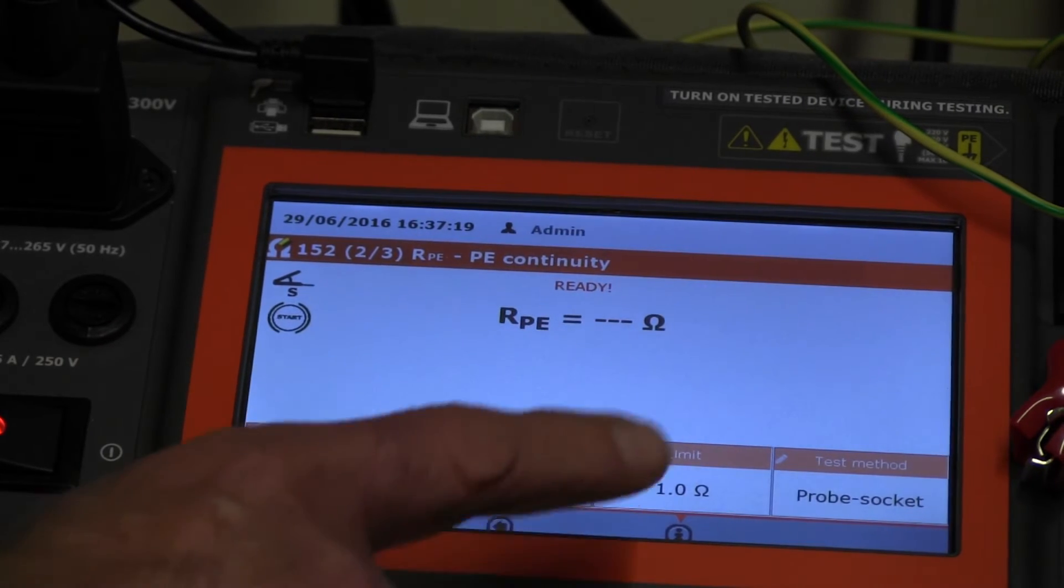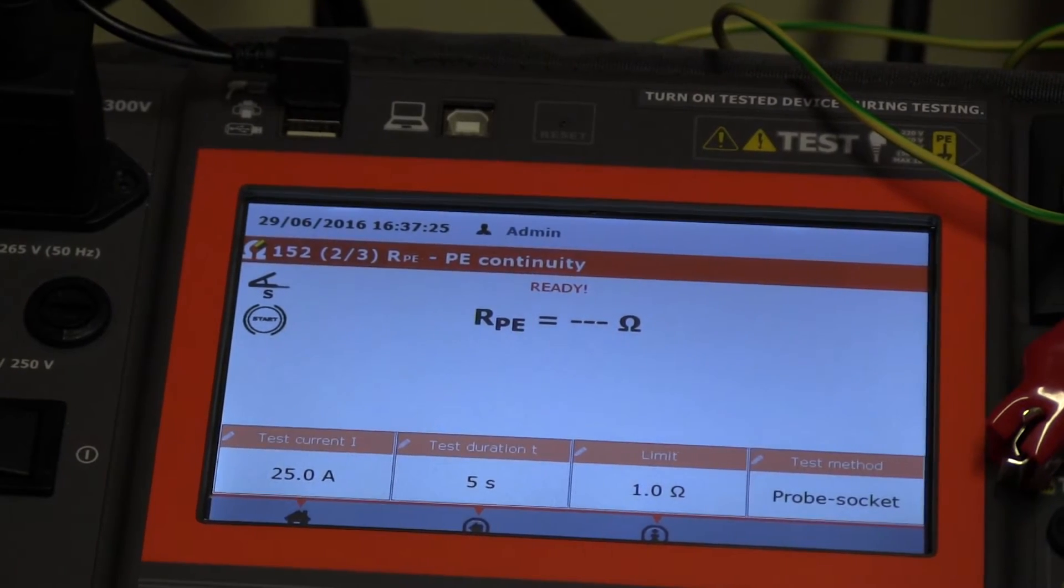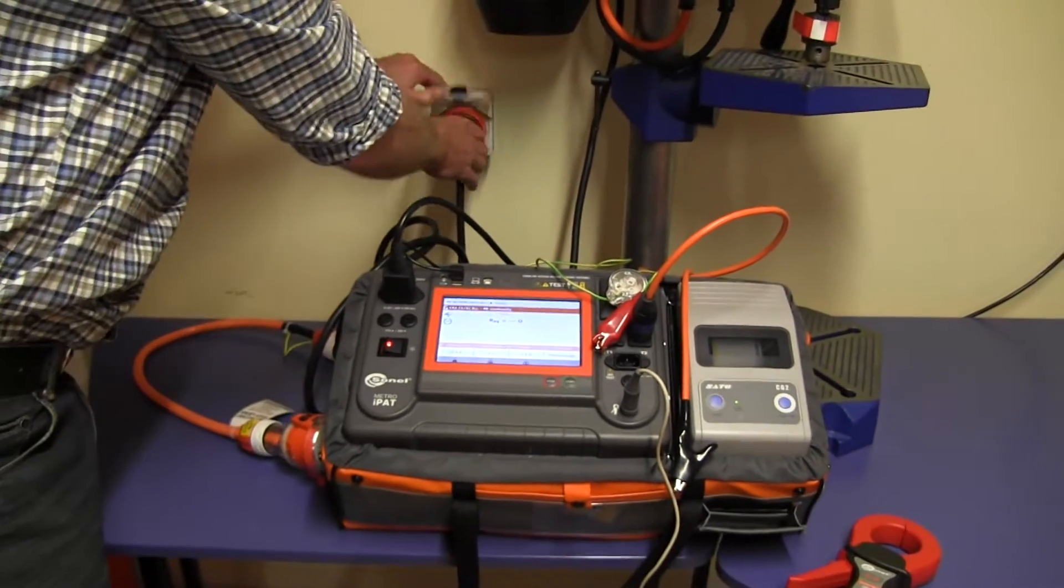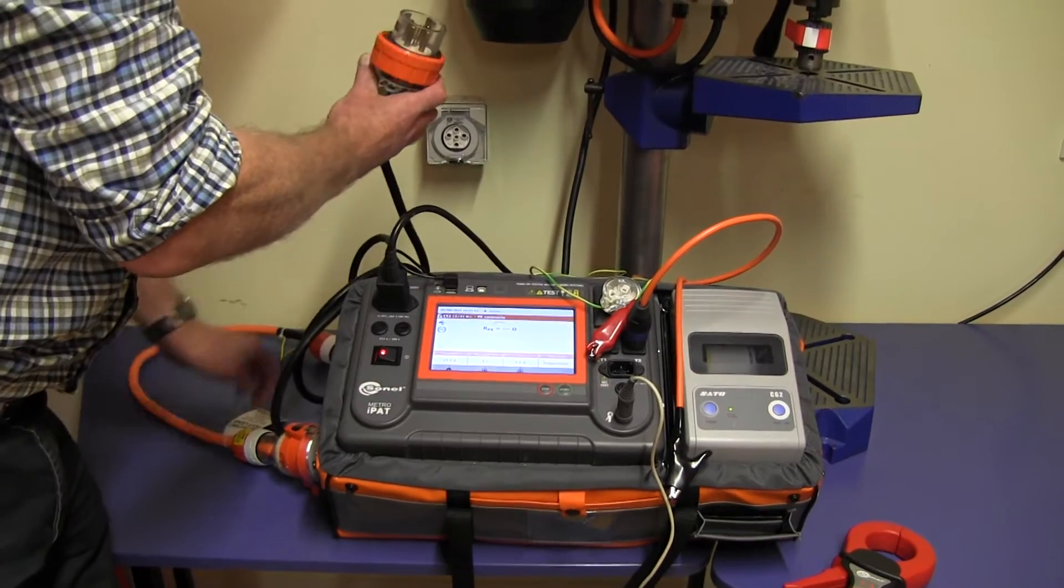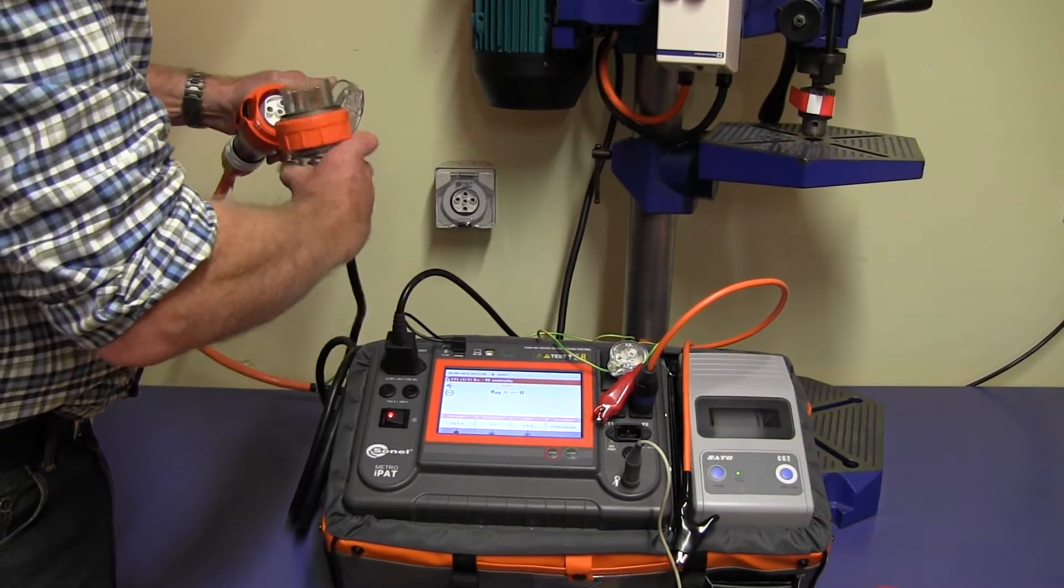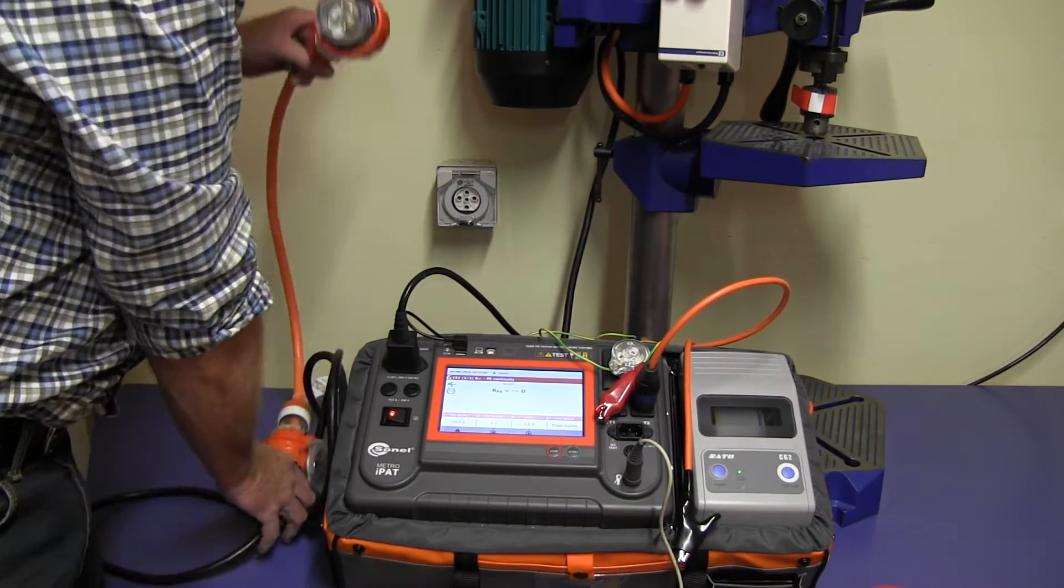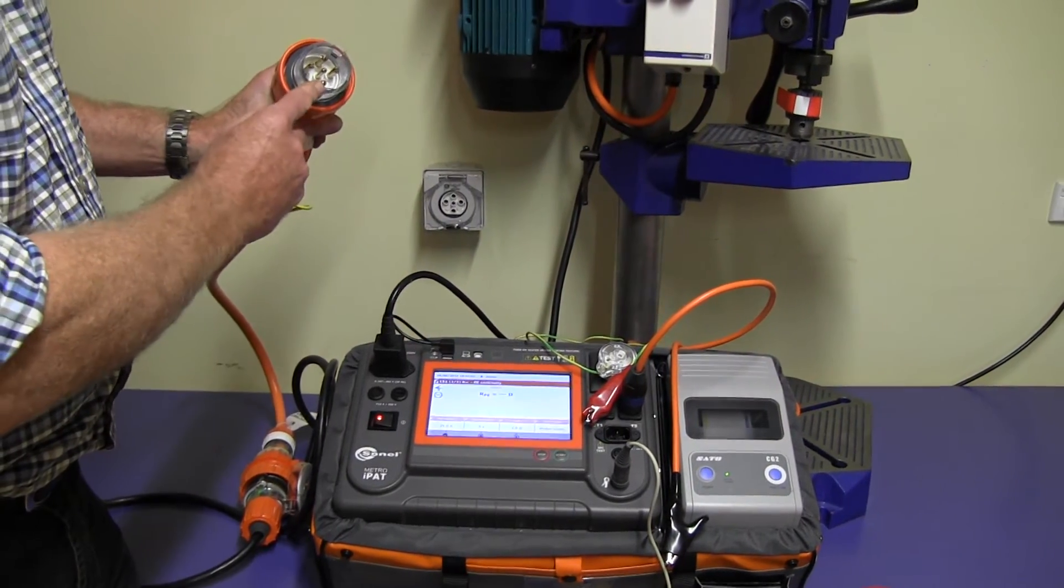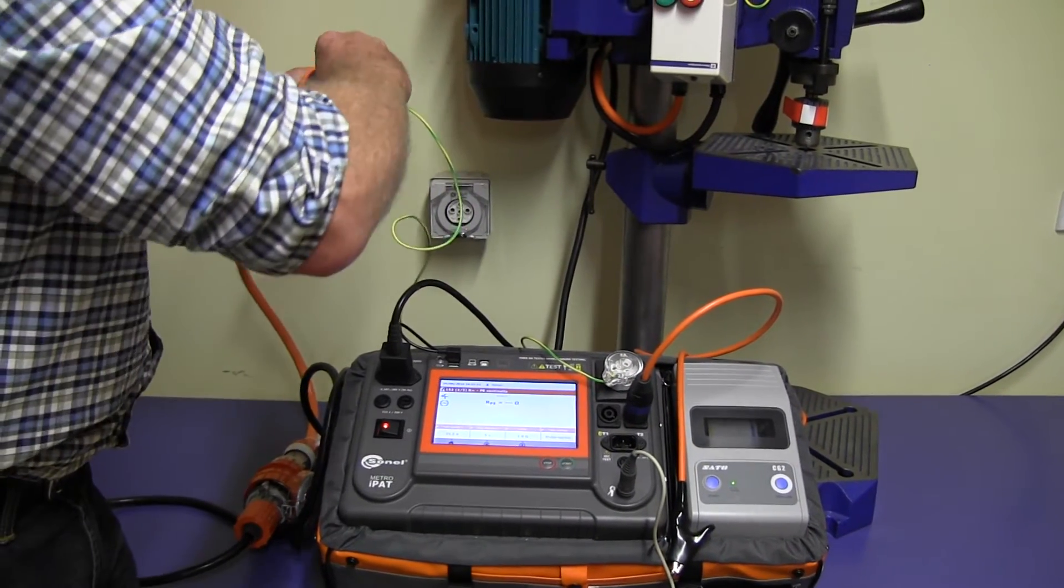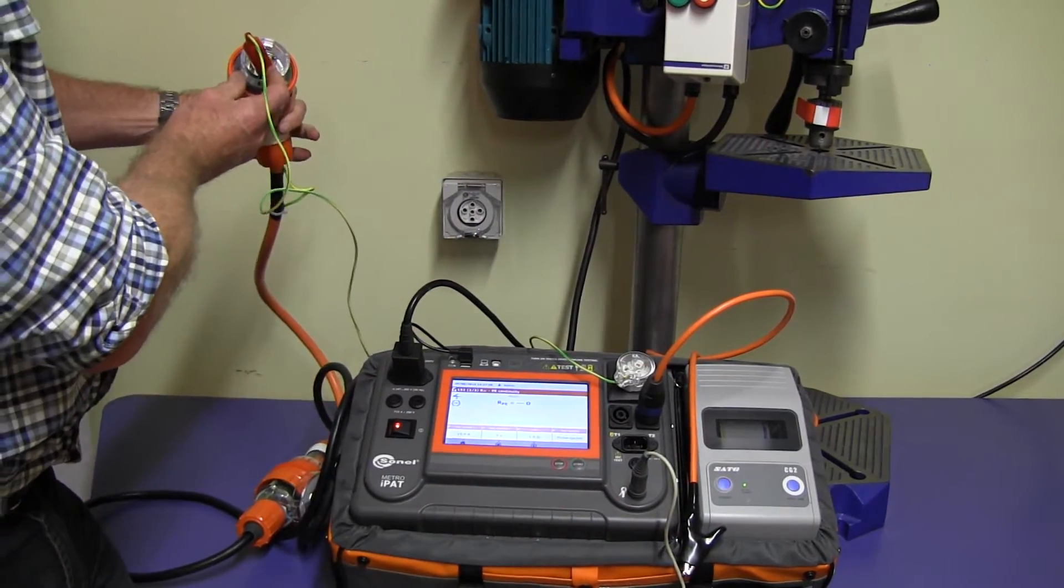The next test is protective earth. At this point we'll add the adapter lead. We need to disconnect the power to the drill press and plug the adapter lead in. Now we're going to measure the earth resistance by putting this on the earth pin here.